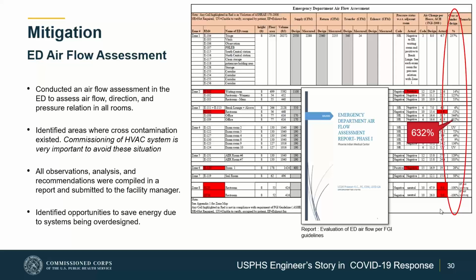In a hospital there are usually only 5 or 10 infection control rooms, depending on the size, but during this unprecedented time there were hundreds of patients on any given day. How do you adjust for that? The general perception is you put those patients in a negative room - to do that you just change the direction of the airflow. If you keep the airflow going from clean to dirty, you'll contain that dirty air in that confined space.